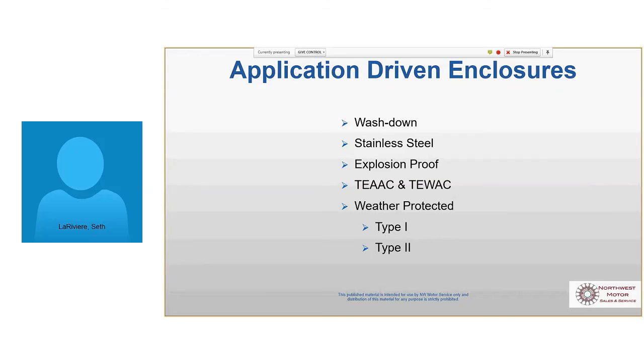If it's a wash down, they make FDA approved paint, food grade. We've got a customer that makes vitamins. They have to use wash down FDA white paint or stainless steel because they can't have any chips of paint falling in the process because it's food. Explosion proof, we see those, grain dust, refineries, lots of things are classified and require special explosion proof motors.